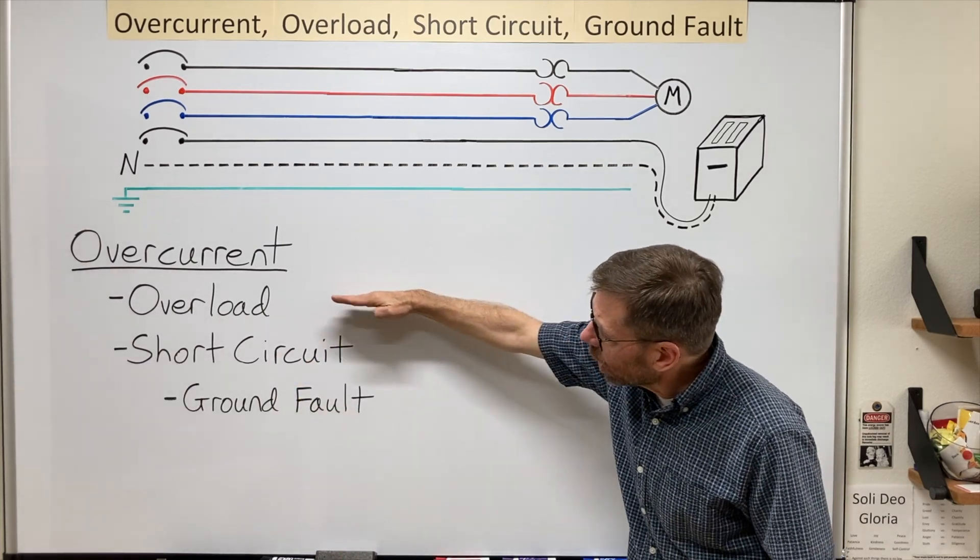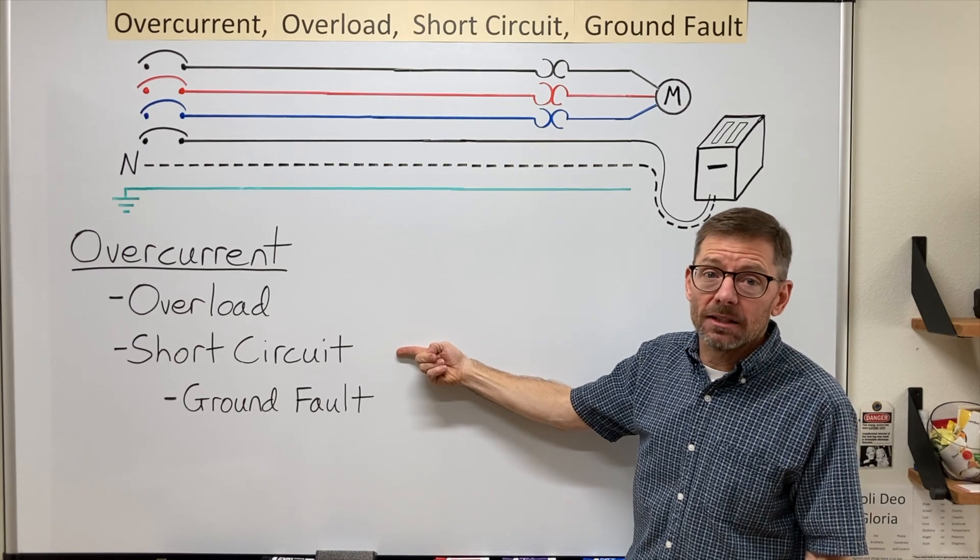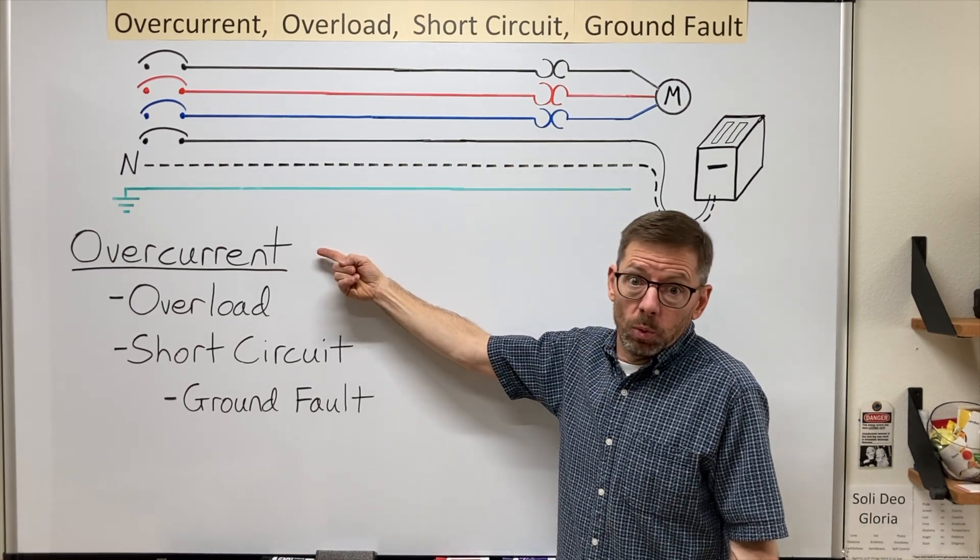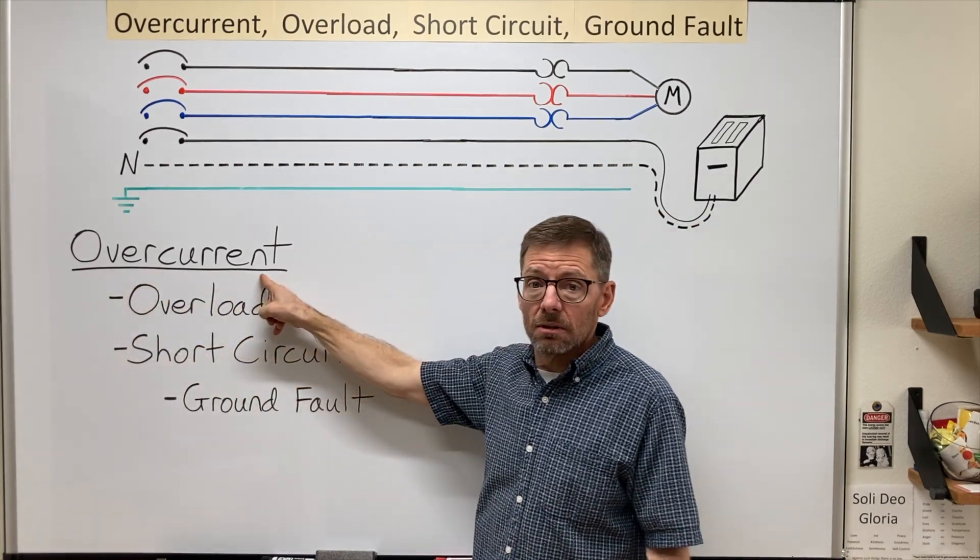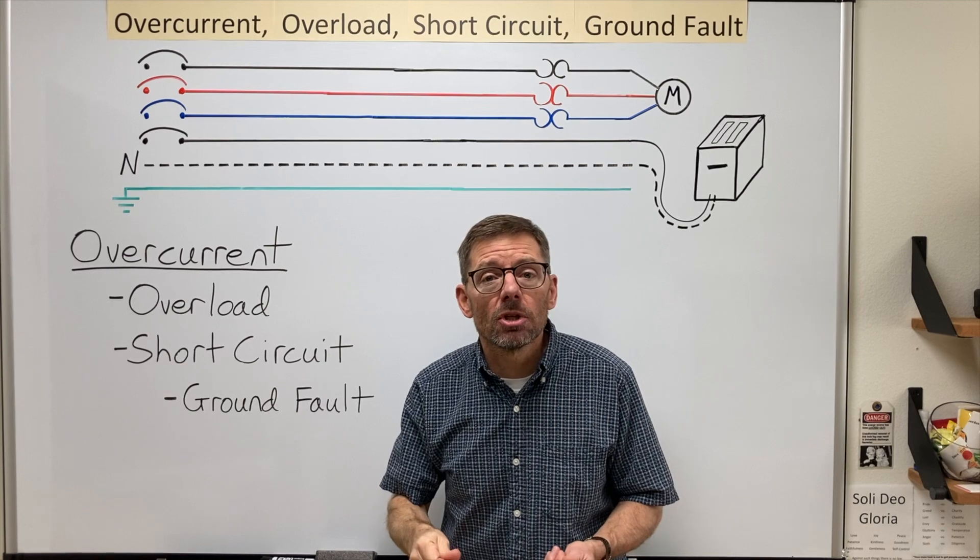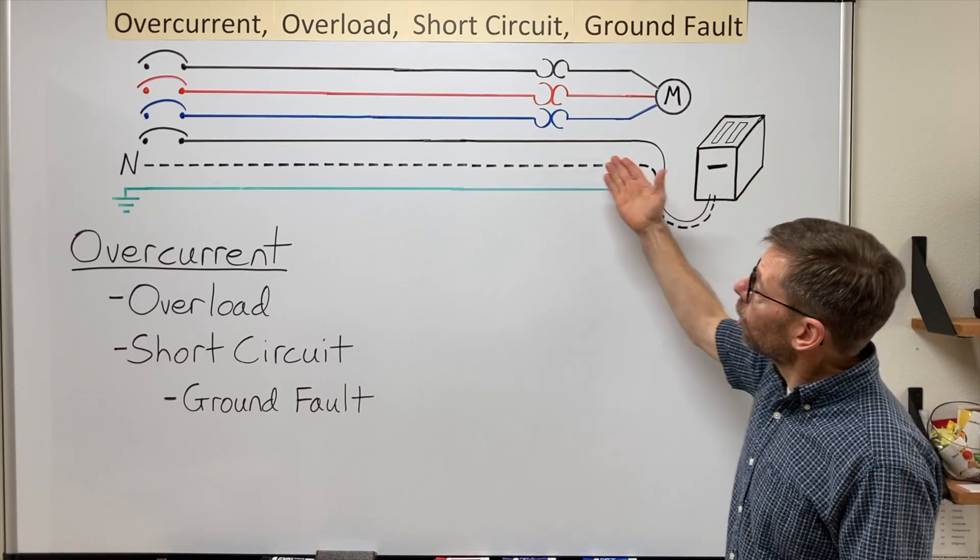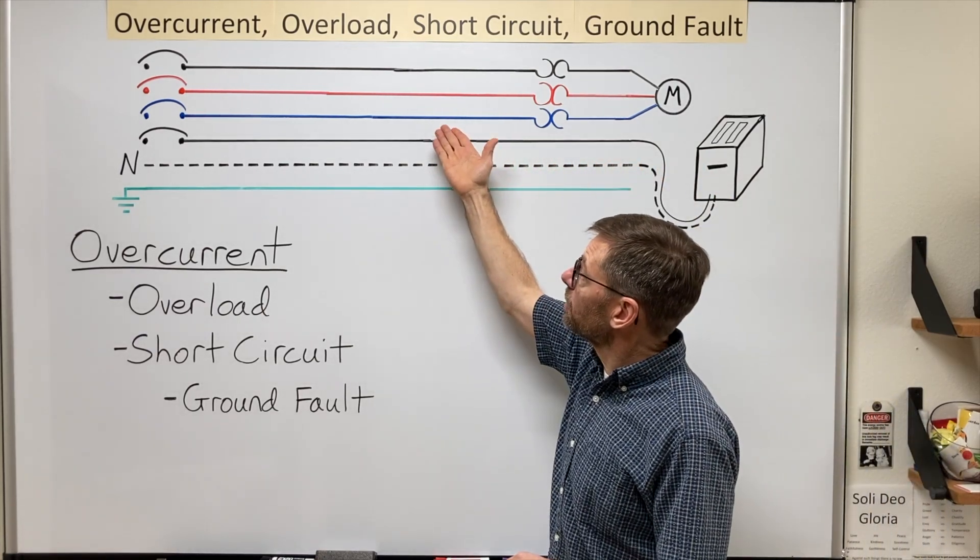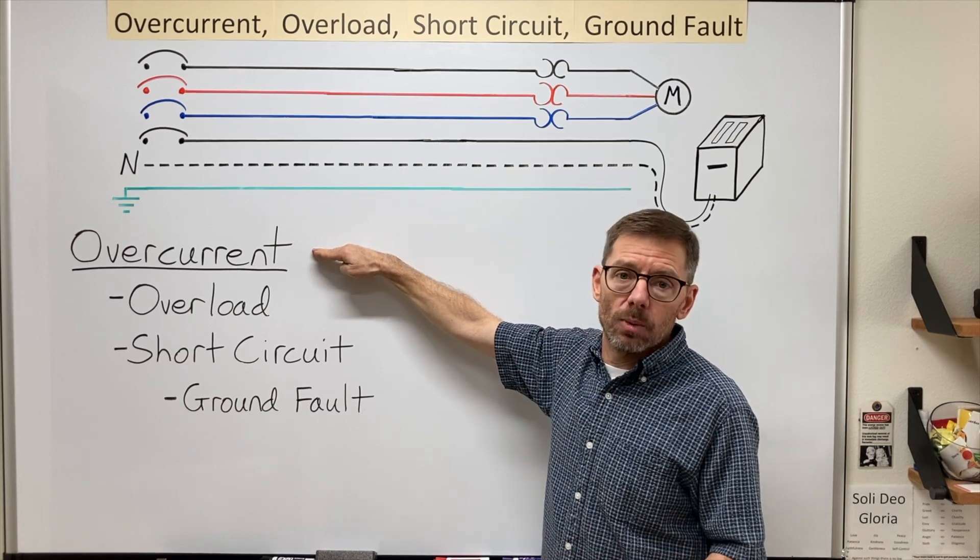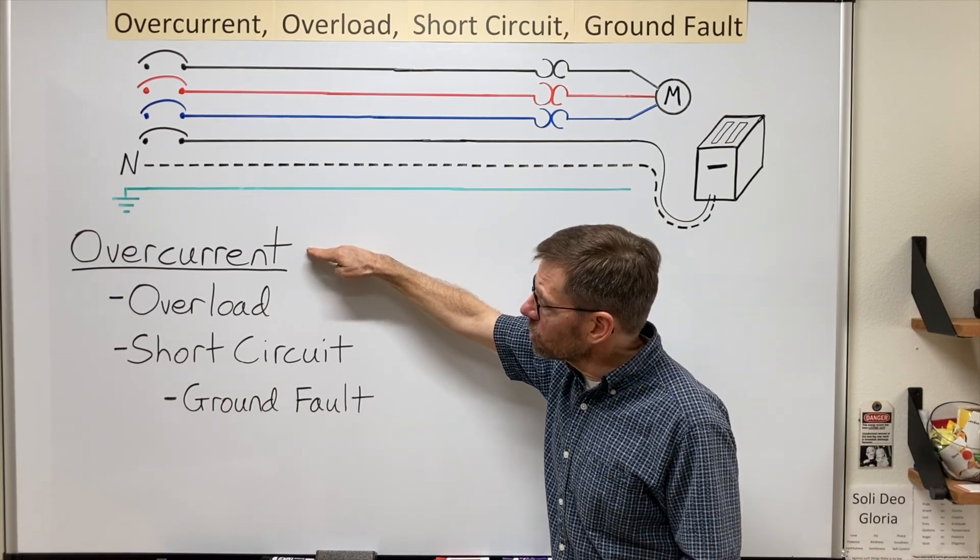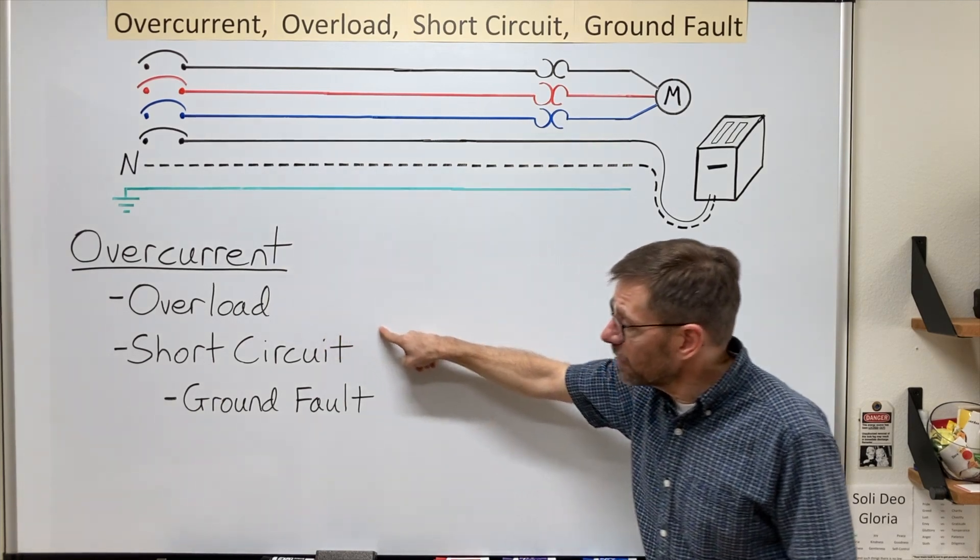Now three of these are defined in the NEC, but short circuit is not. Let's just start with overcurrent. We'll break apart the word: too much current. Whenever we have a situation where we have more current than a piece of equipment is rated for or than the ampacity of a particular conductor, we have an overcurrent situation. And the definition goes on to tell me that these overcurrents can result from any of these three.